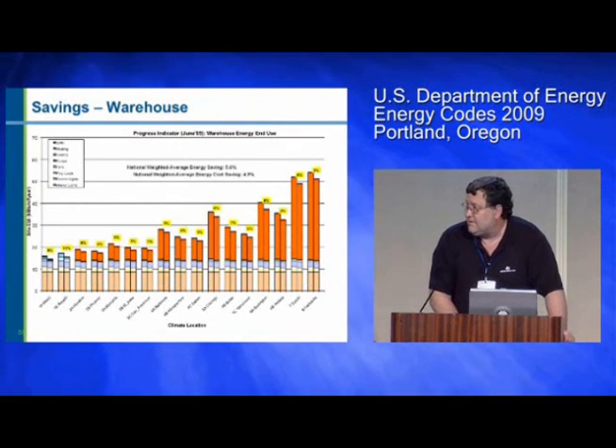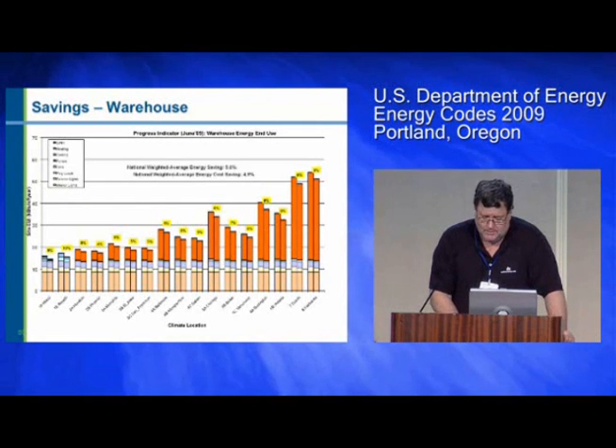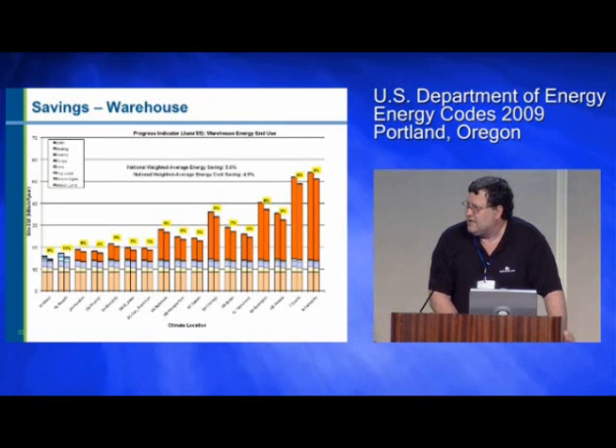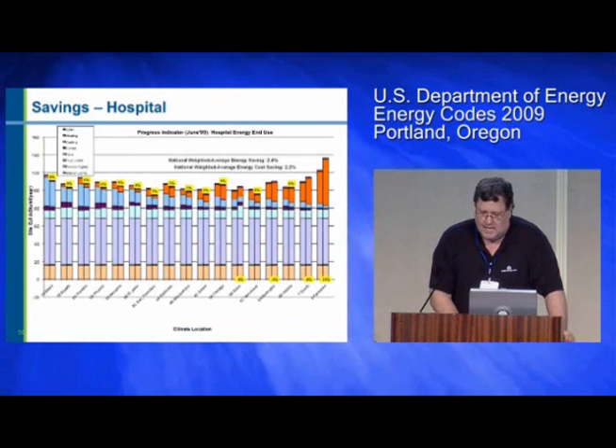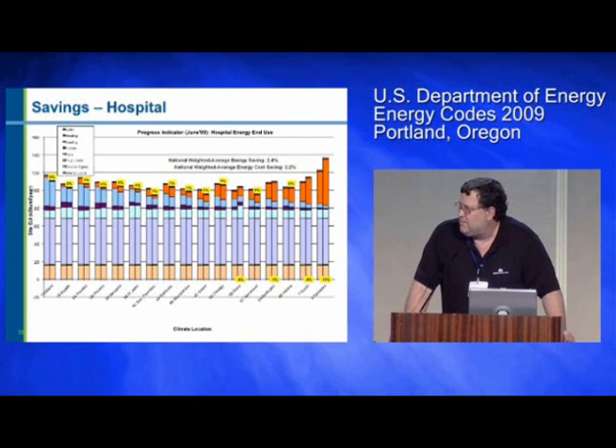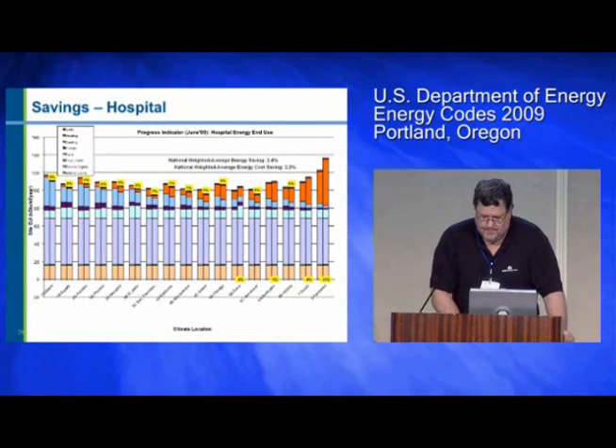Warehouses, savings aren't as big in warehouses. It's tougher to do things in warehouses. You don't have as many levers to push in a warehouse. There's just not as much going on. Hospitals, very complicated buildings. Savings are low. Part of that is driven by the fact that the ventilation requirements in hospitals are pretty high, and that tends to outweigh anything you do to the building envelope, to the lighting.